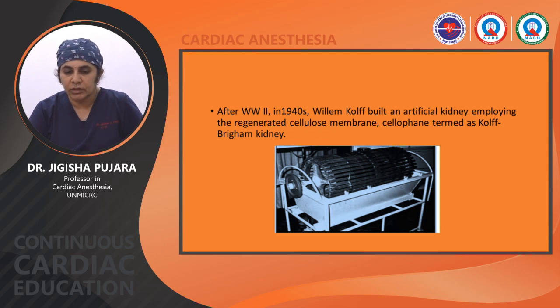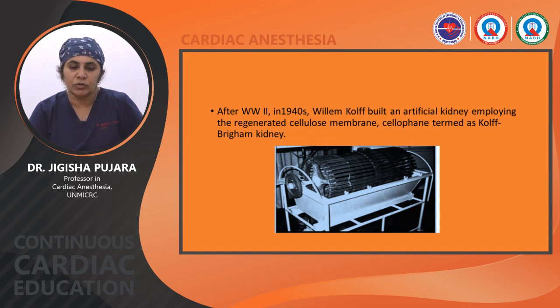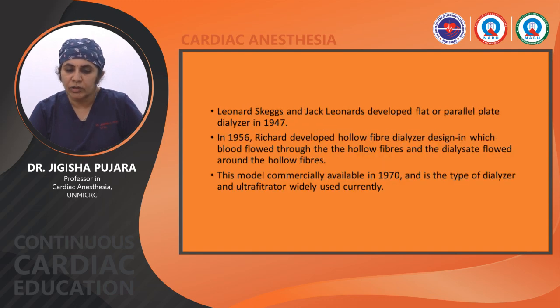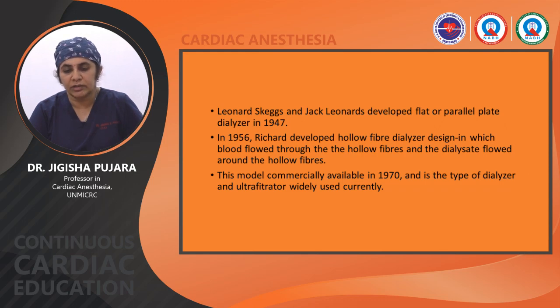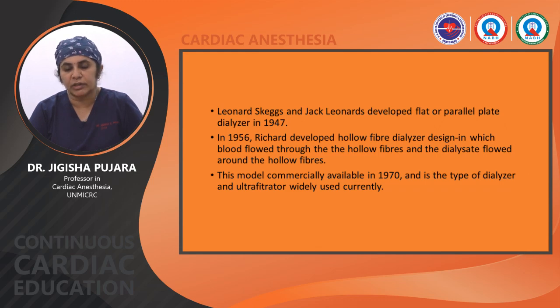In 1913, John Abel first reported dialysis where blood circulated outside the animal, and anticoagulant hirudin from the leech was discovered to prevent coagulation. After World War II in the 1940s, William Kolff built an artificial kidney employing the regenerated cellulose membrane — cellophane — termed the Kolff-Brigham kidney. Leonard Skeggs and Jack Leonards developed a flat or parallel plate dialyzer in 1947. In 1956, Richard developed a hollow fiber dialyzer, commercially available in the 1970s, which is the type widely used currently.